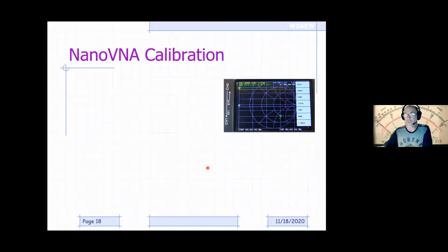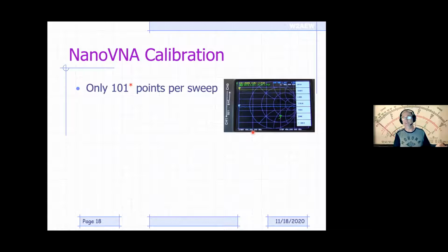So let's walk through a little bit more detail on the calibration, and this will help us walk through some of the menu structures too. I want to give you a couple of details on the calibration here, again emphasizing why it's important. Most of the NanoVNAs only contain 101 points in the frequency sweep. So you might just say, well, I'll calibrate it from 1 megahertz to 450, and I'll never have to calibrate it again because that encompasses everything from VHF and UHF, and most of what I'm going to use, right?